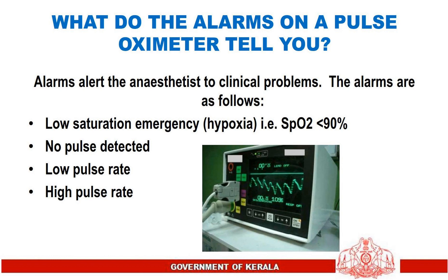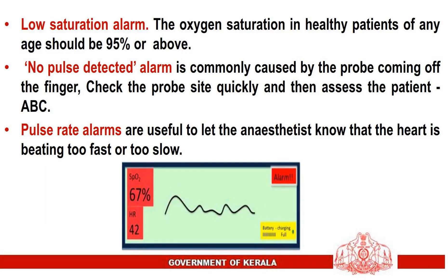What do the alarms on a pulse oximeter tell you? Alarms alert the anaesthetist to clinical problems. The alarms are as follows: low saturation emergency — hypoxia, that is SpO2 less than 90%; no pulse detected; low pulse rate; high pulse rate. The oxygen saturation in healthy patients of any age should be 95% or above. A 'no pulse detected' alarm is commonly caused by the probe coming off the finger — check the probe site quickly then assess the patient's ABCs. Pulse rate alarms are useful to let the anaesthetist know the heart is beating too fast or too slow.